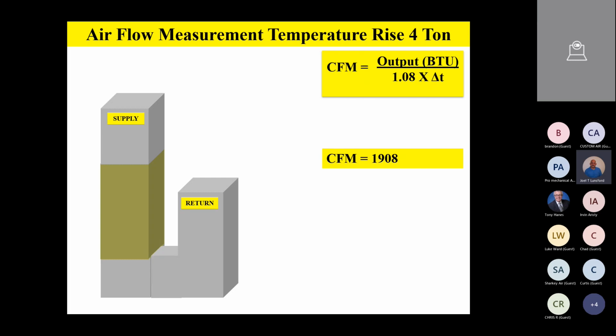So in this example, let's say I'm on speed tap number 5. Maybe it's a brand new install and the air handler comes from the factory on high speed tap for cooling. That's very common. We do that on the Champion side because we don't know what kind of ductwork it's going to be installed with. So we always place our cooling tap typically on high speed. Well, you might have a really nice, open duct system, well designed and so on.